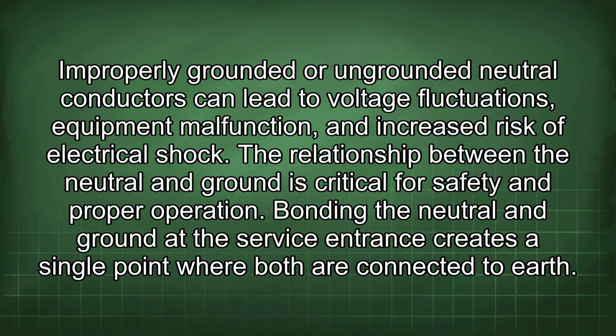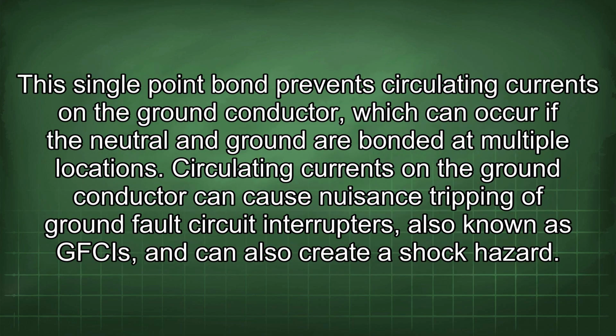The relationship between the neutral and ground is critical for safety and proper operation. Bonding the neutral and ground at the service entrance creates a single point where both are connected to earth. This single point prevents circulating currents in the ground conductor, which can occur if the neutral and ground are bonded at multiple locations. Circulating currents on the ground conductor can cause nuisance tripping of ground fault circuit interrupters, also known as GFCIs, and can also create a shock hazard.